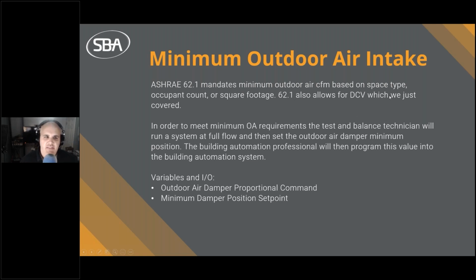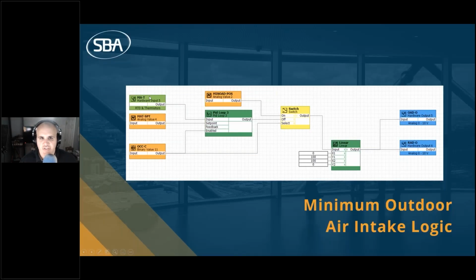And what happens essentially is that the test and balance tech is going to run a system at full flow, and then they're going to set the outdoor air damper minimum position. Then the building automation professional is going to take that value and put it in the BAS. Or if it's smart equipment, it's just going to be put in the equipment under one of the AV values, analog values. The variables typically are outdoor air damper proportional command and minimum damper position set point. So this is pretty easy to code, pretty easy to set up. Real simple. Most of the time, I do this in conjunction with mixed air temp for economizer.